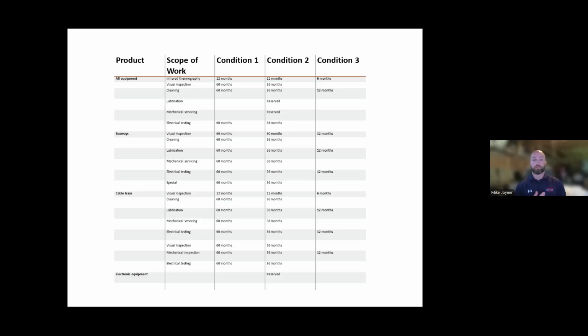Condition one would be once every 5 years, condition two is once every 3 years, and they recommend doing the de-energized maintenance then. Condition three, on the far right, calls for a de-energized maintenance cleaning once a year until you get back up to par into condition two.